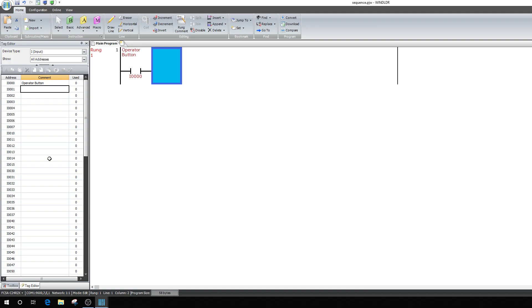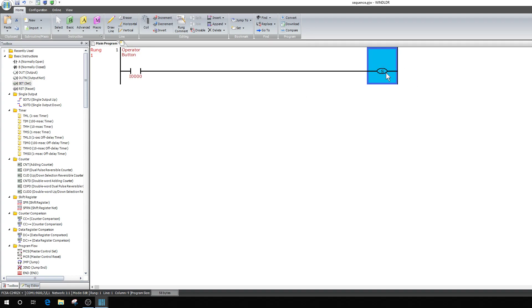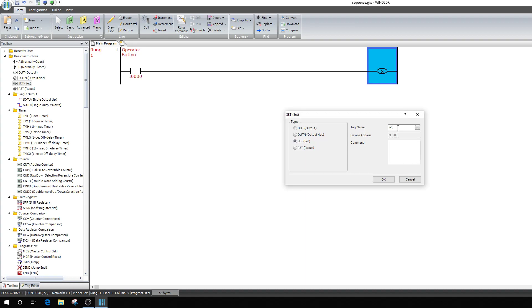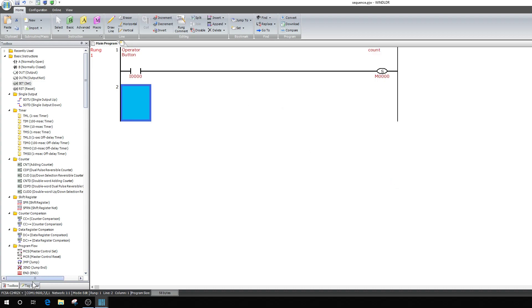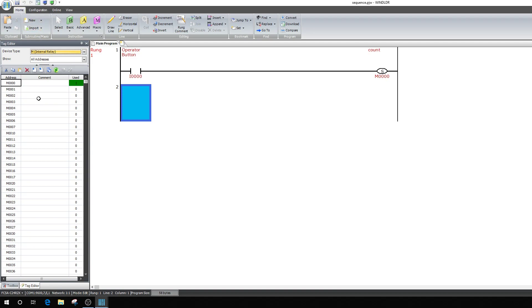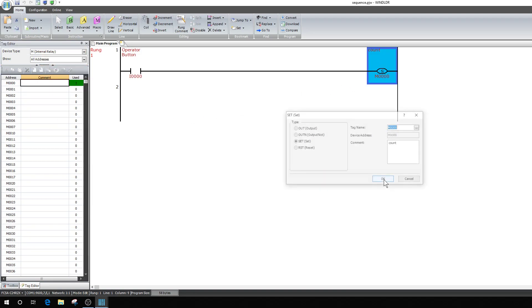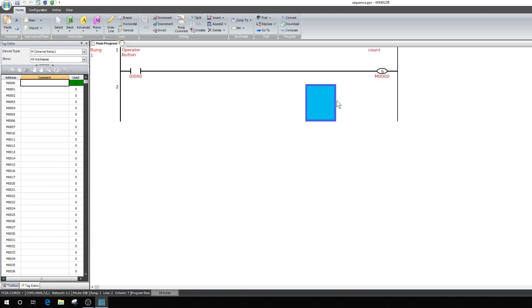I'm going to grab a SET output. That's an output that stays on — when this momentary button is pushed and released, this will remain on. I'm going to call that M0 and name it 'Start Count.' If I go over to the tag editor and go to memory bits — I'll save first. There seems to be a glitch with the IDEC software where the comment doesn't always appear right away.